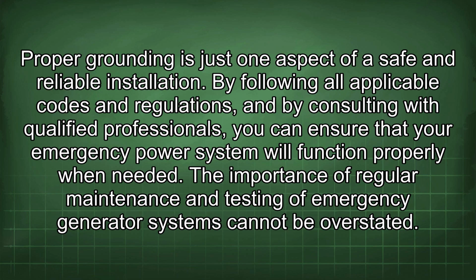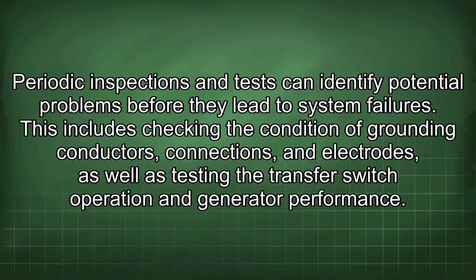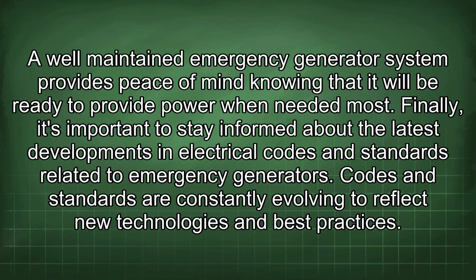The importance of regular maintenance and testing of emergency generator systems cannot be overstated. Periodic inspections and tests can identify potential problems before they lead to system failures. This includes checking the condition of grounding conductors, connections, and electrodes, as well as testing the transfer switch operation and generator performance. A well-maintained emergency generator system provides peace of mind knowing that it will be ready to provide power when needed most.